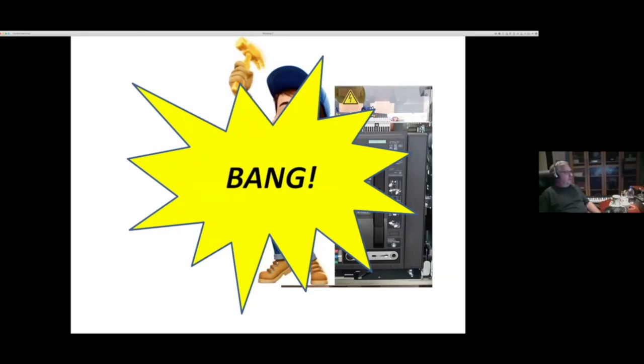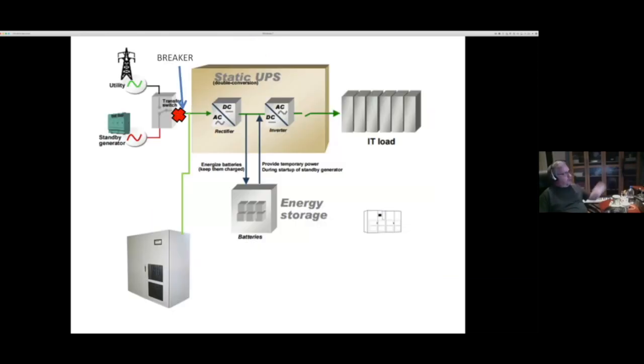It scares the crap out of anybody nearby and requires special equipment to replace. Well, I say replace because these guys tried - there's where the breaker was right there. So obviously the first thing you do is go get your protective gear, right? Because you're dealing with 400 amp AC power.